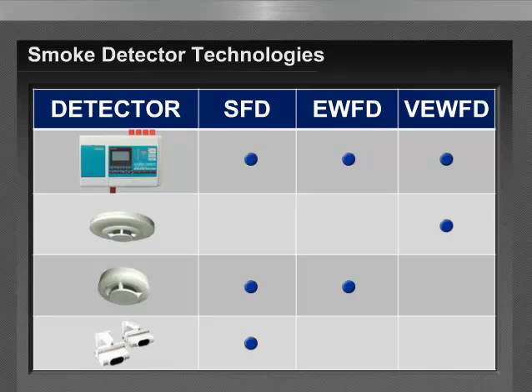So we've now learned the three detection classification categories, and our next step is to understand the various detector technologies that fall into each category. There are essentially four types of smoke detection technologies that we'll consider in this discussion as we're talking mission-critical data center telecommunication. And with that, we look at such technologies as beam type detection, and when we see beam type detection, we look at the standard fire detection category in terms of its sensitivity. And then next in line is conventional spot type smoke detectors, and this might include the likes of photoelectric and ionization type smoke detectors.